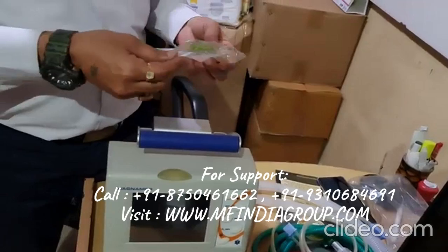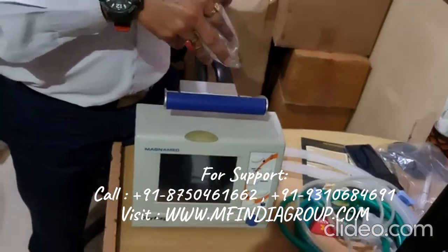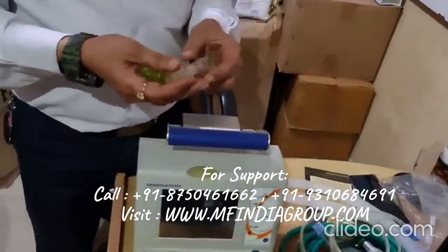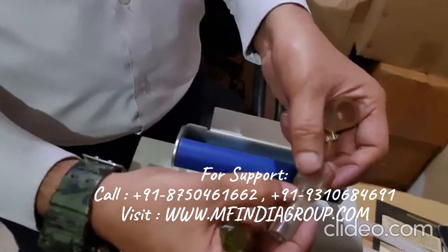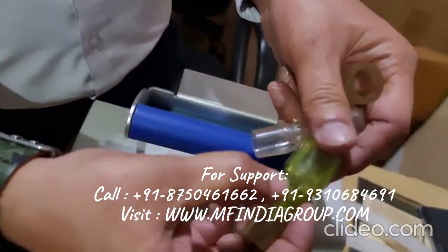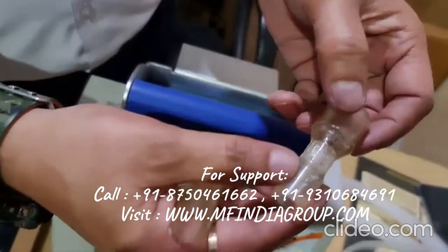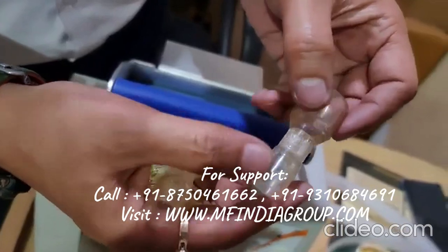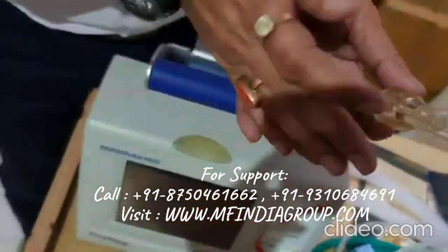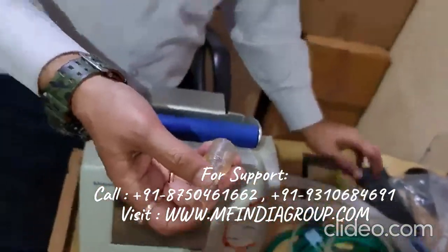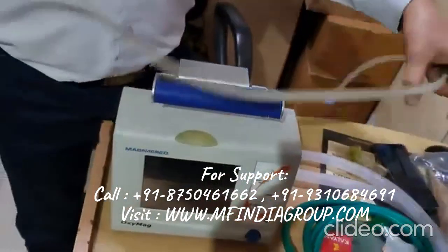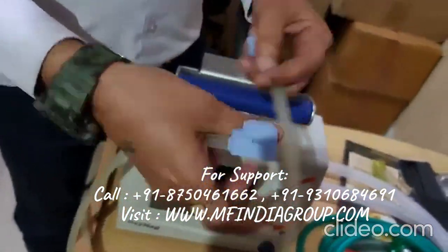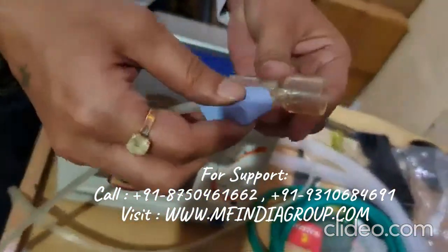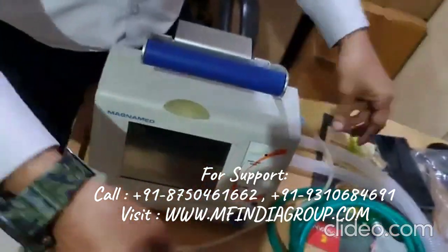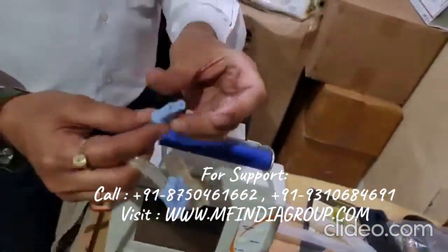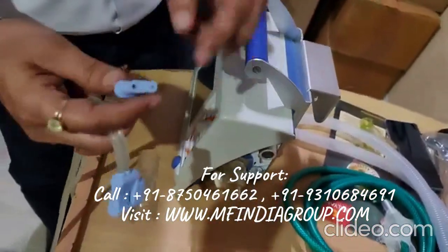It's a neonatal to adult ventilator. We have different flow sensors for different patients. Here it is written: infant, neonatal, and this is the adult flow sensor. So according to your patient, you have to choose your flow sensor. These are reusable polycarbonate flow sensors. This is the sensor line. This is the patient end. It can be connected here like this, and this is the ventilator end. So you have to connect according to their holes.